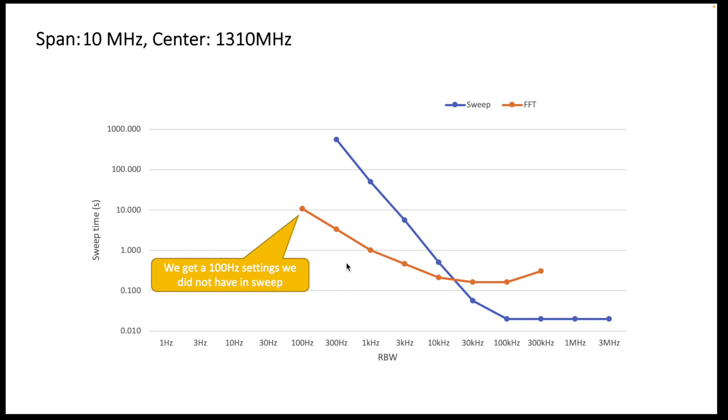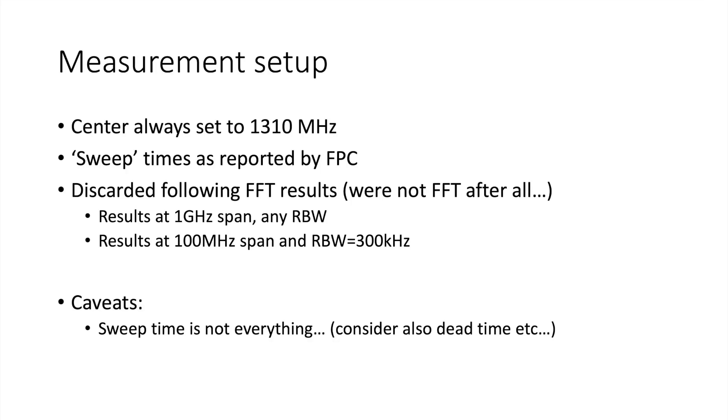Now I also did this exercise looking at different span ranges so we get a more full view. So let me just quickly take you through the measurement setup. For all the analysis that will follow, the center frequency is always set to 1.31 gigahertz. I chose this value so I can both do a very wide span of over a gigahertz and much smaller spans. Then I'll also always be showing you the sweep times as they are reported by the spectrum analyzer.